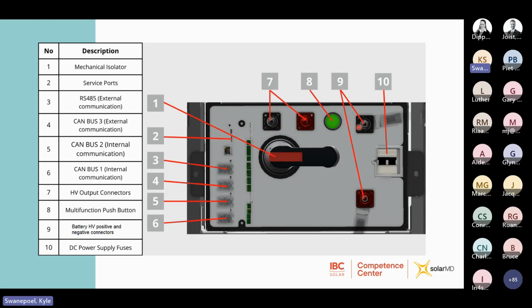And then you have the multi-function push button. This push button serves a similar function to that on the low voltage battery. You've also got indication LEDs over here and over here, which will be the same as your BMS LEDs. So there is functionality behind this button as well, and this is also where you'll turn the communication of the BMU on. And then you've got your battery input connectors over here. These are your HV input connectors from your battery modules. And then number 10 is just the power supply fuses for the communication boards. All right.